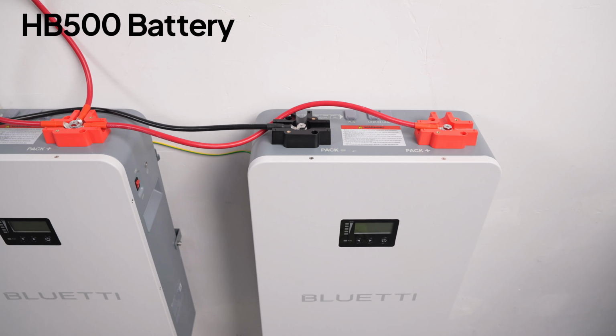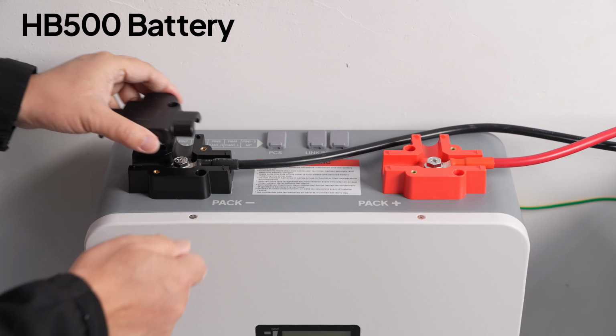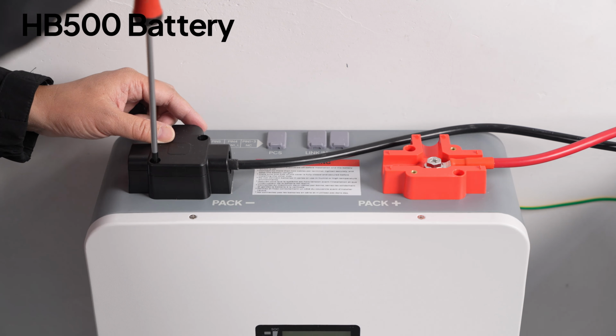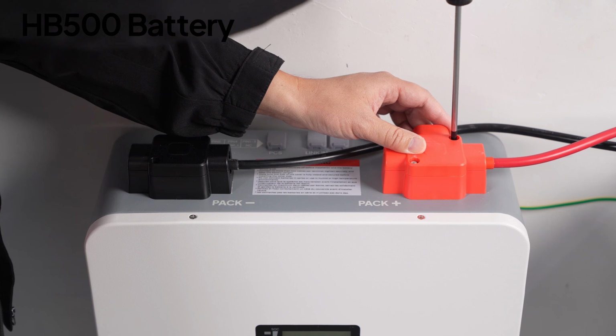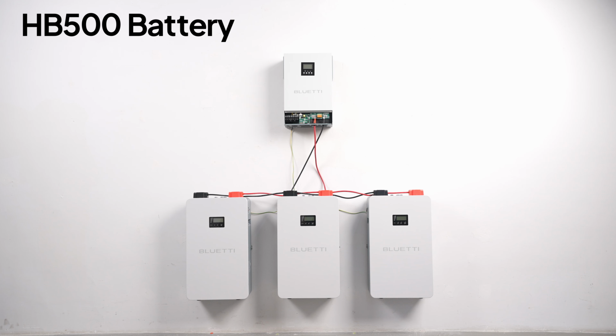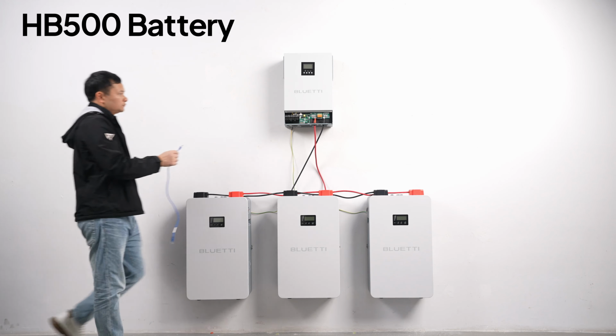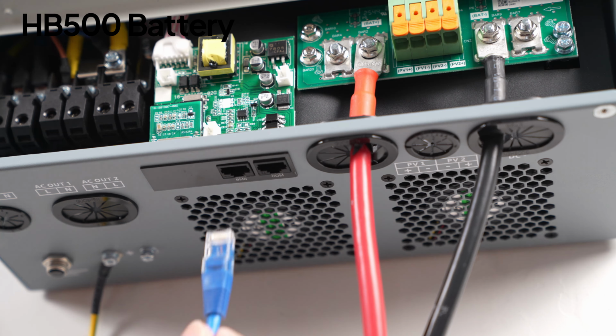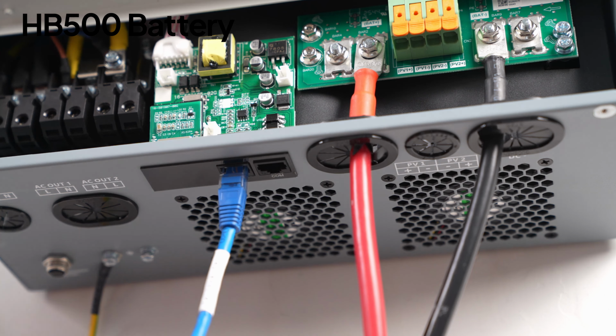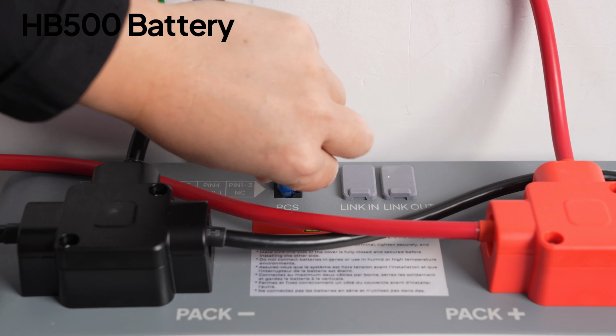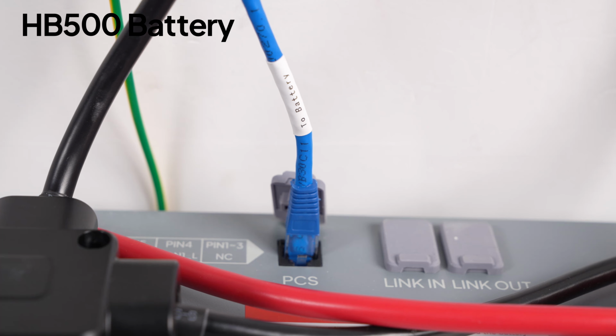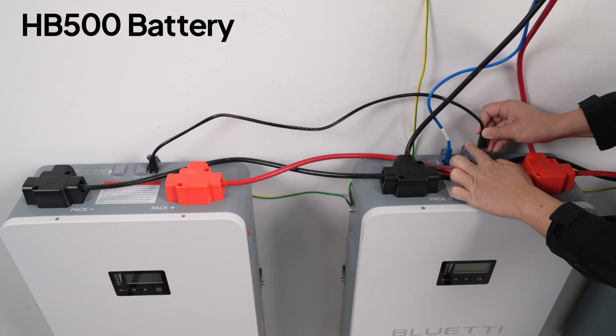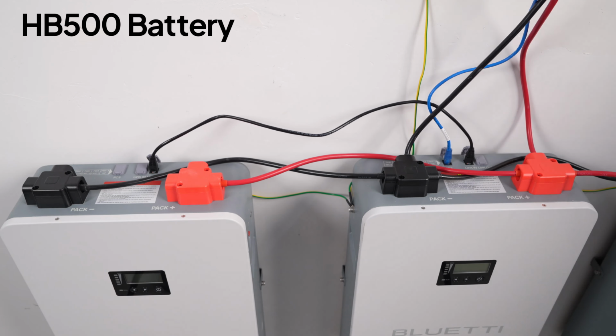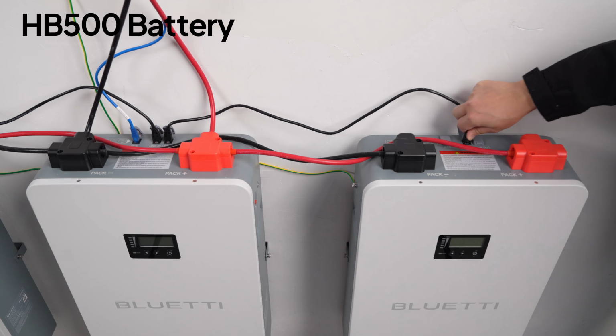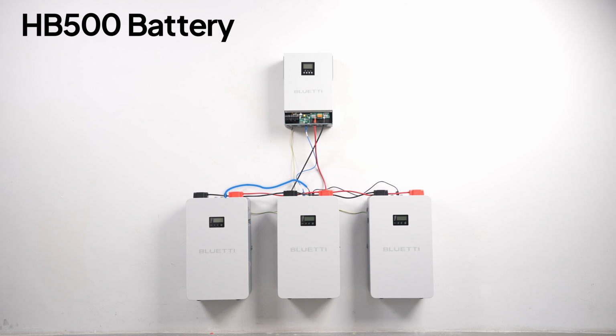Remove the tabs from the top covers, then reinstall the covers. Next, connect the communication cables. Plug the to inverter end into the BMS communication port on the HV10K, and the to battery end into the PCS communication port on the HB500. Then link the batteries by connecting link out to link in. Take a moment here to double check all connections, they should be tight and correct.